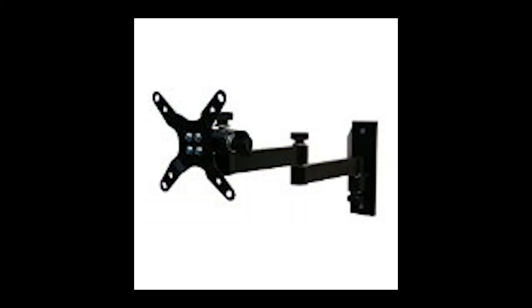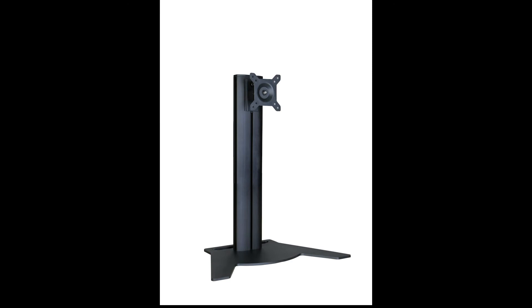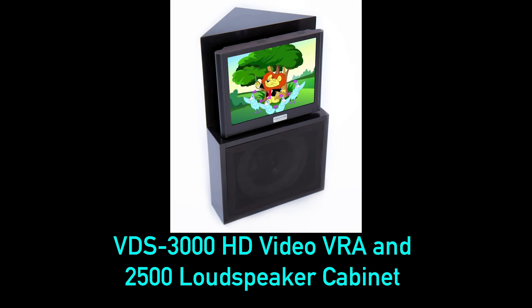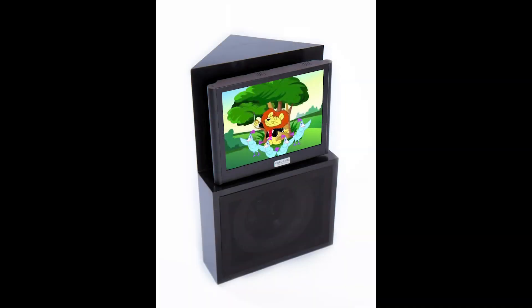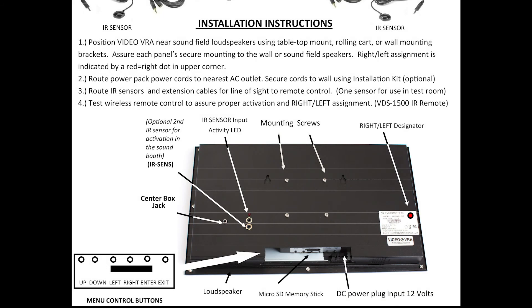To install the VDS 3000 video VRA system, it comes with dual arm mounting brackets which are included to mount directly to the wall with easy repositioning of the monitor to the desired position. The VDS 3000 video VRA can also be mounted using a desktop stand or roller stands for portability, or to use in multiple rooms. They can also be integrated into a compact, elegant loudspeaker that blends the VRA system into a small footprint when in use and hides it when testing adults. The next step is to run the power supply cables from the outlet in the test room to each reinforcer monitor. The optional video installation kit includes 15-foot power cables to accommodate larger rooms.